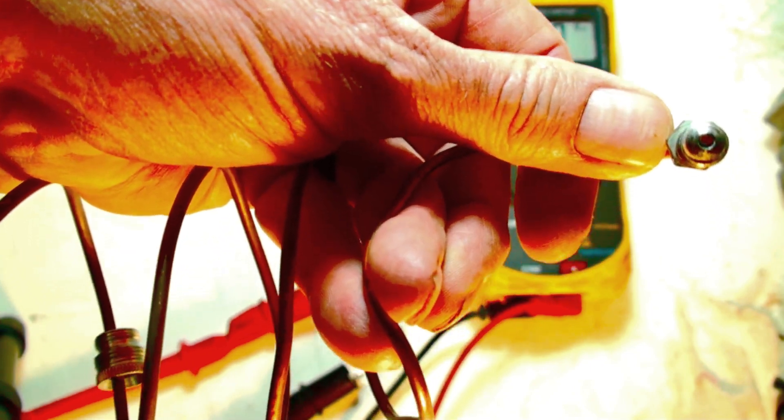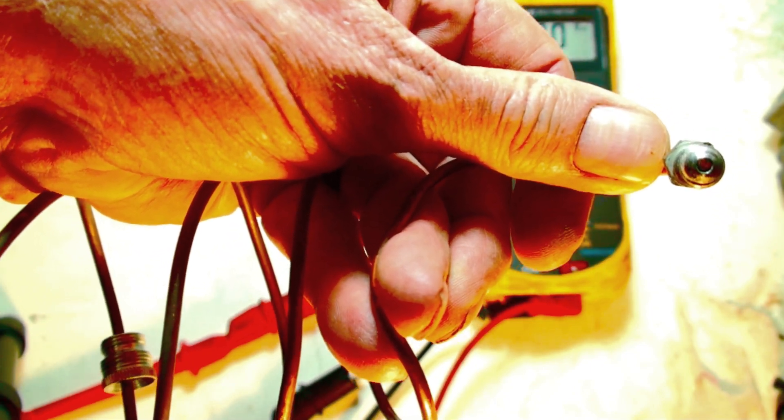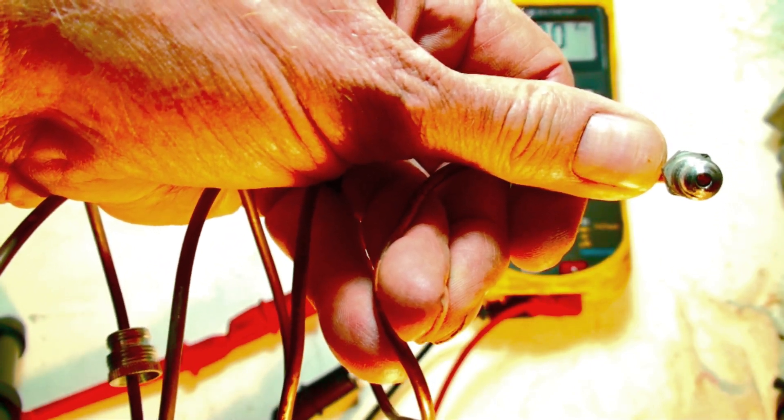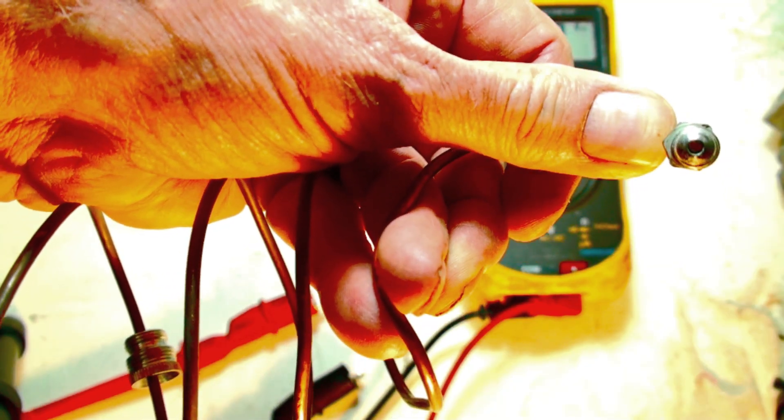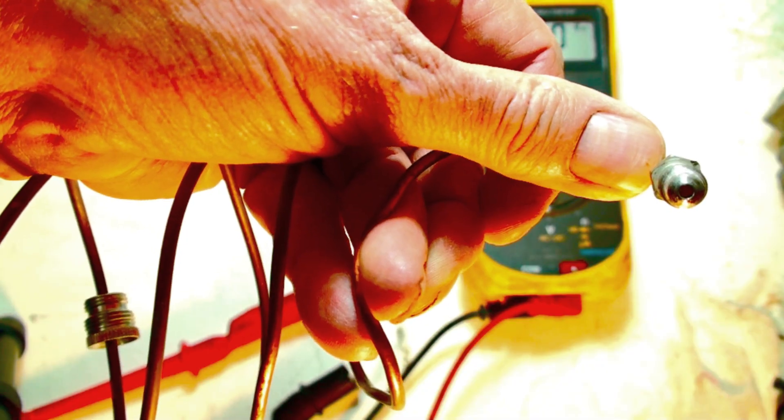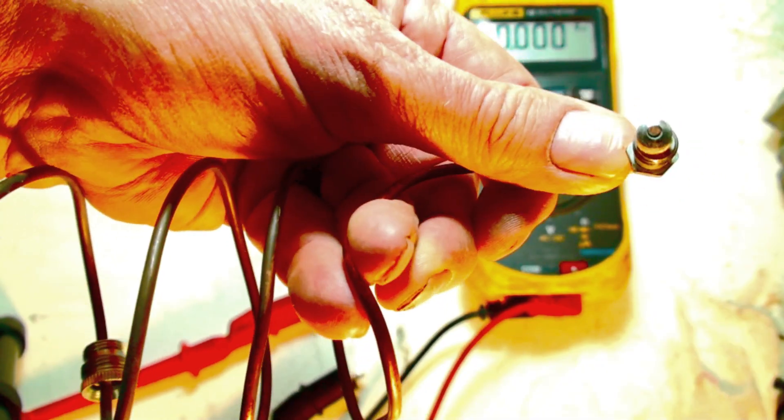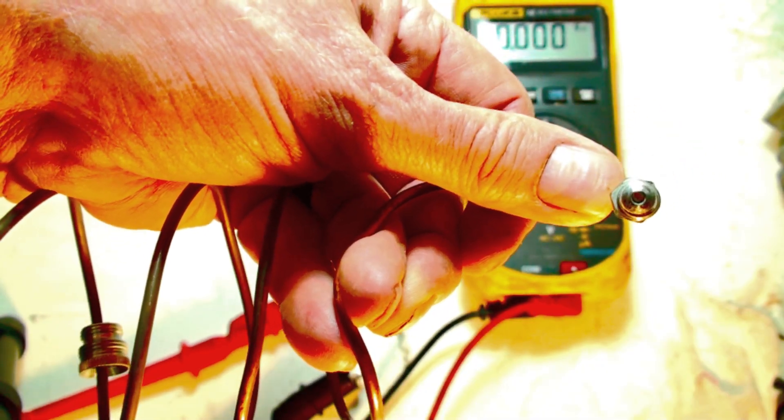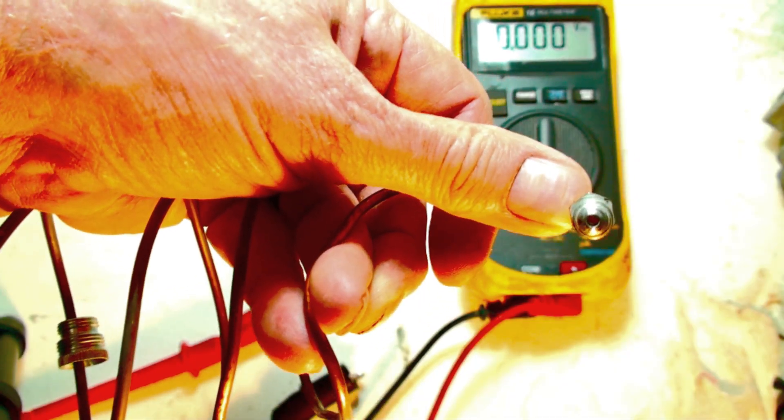That button needs to have very good contact, so it needs to be clean. It does not need to be sanded—do not sand this thing. Take and rub the end of it on your shirt sleeve. That works really good to clean these up. See, we're only dealing in up to 30 millivolts.